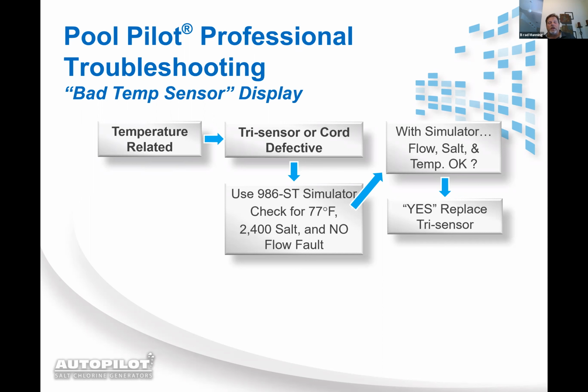If you plug the simulator in and the message doesn't go away, you first need to check to see if the unit's out of calibration and needs calibration. If you calibrate it and it doesn't hold the calibration, you know you've got a bad part. You've either got a bad 848 board, a bad ribbon cable between the 848 board and the 830 board, or you've got a bad 830 board, which once again is the digital display board.